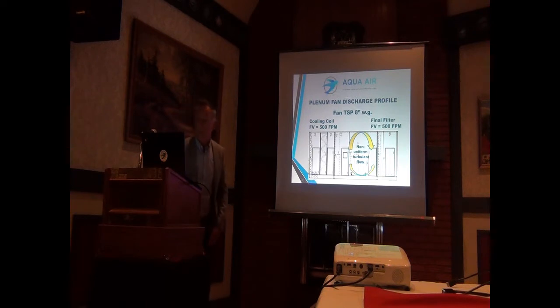One good thing about pressurization fans like this, you can have multiple. It's not shown here, but you could have 2 in the ground, 2 in the end, 1 in the roof. Any combination that you would need or could dream of, you can put more openings on in there. This tends to be a little bit, because you don't have that discharge distance that you have to watch, the footprint be a little bit smaller than if you're using the standard fan that we looked at in the past.